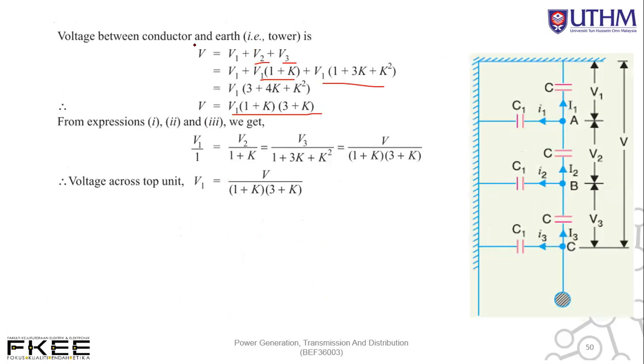Okay, let's check the voltage between conductor and earth, that is the tower. So the total voltage V is equal to V1 plus V2 plus V3. V1 is V1, V2 is V1 (1 plus K), V3 is V1 (1 plus 3K plus K square). So we got V equal to V1 (3 plus 4K plus K square), and we simplify, we got V equal to V1 (1 plus K)(3 plus K).